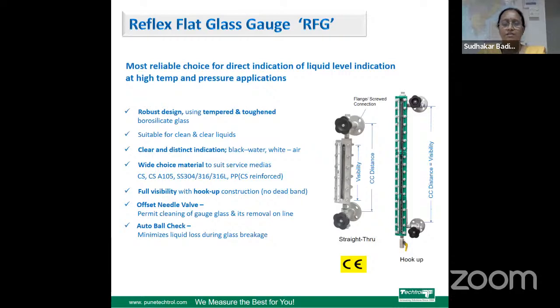This is a reflex flat glass gauge. This is the most reliable gauge, which is used for direct indication of liquid level for high temperature and high pressure application. It is a robust design which uses a tempered and toughened borosilicate glass. It is suitable for clean and clear liquids. The process connections are available in flange and screw connection. This gives a clear and distinct indication of water level in black color, whereas air or steam is in white color. So you can see the liquid level with very clear indication.